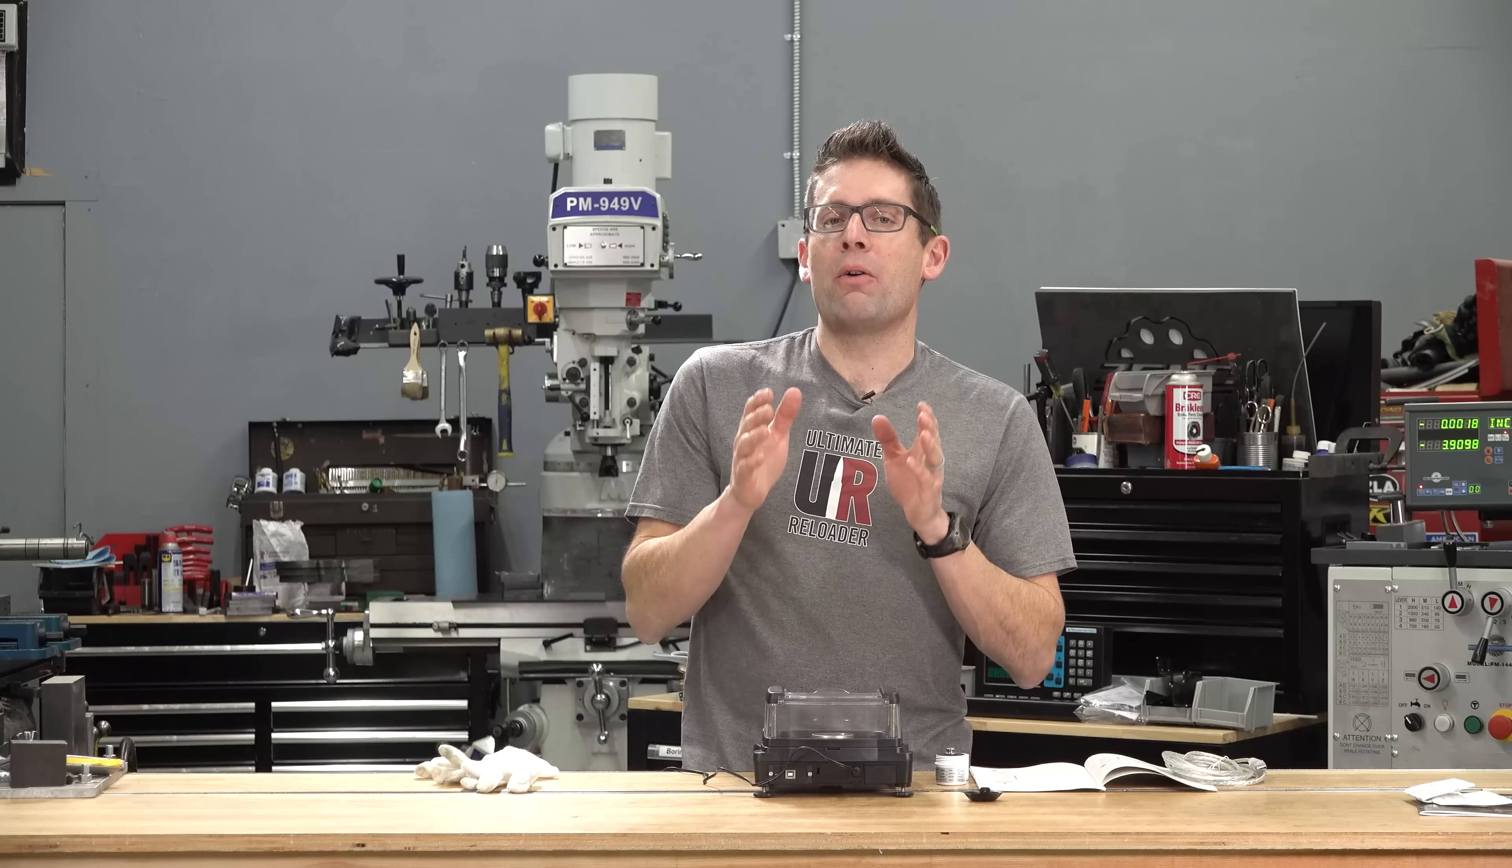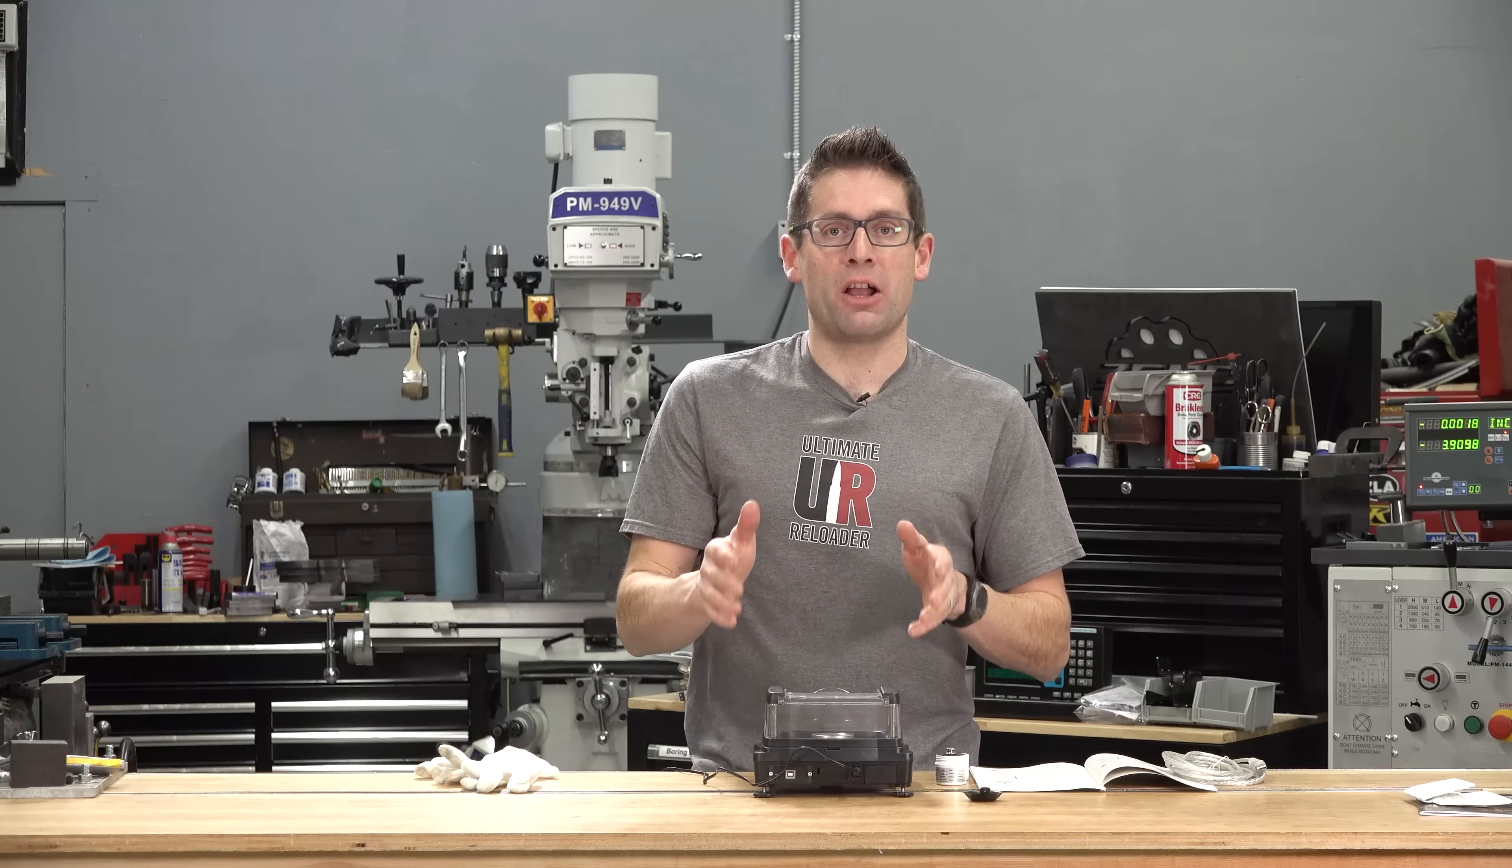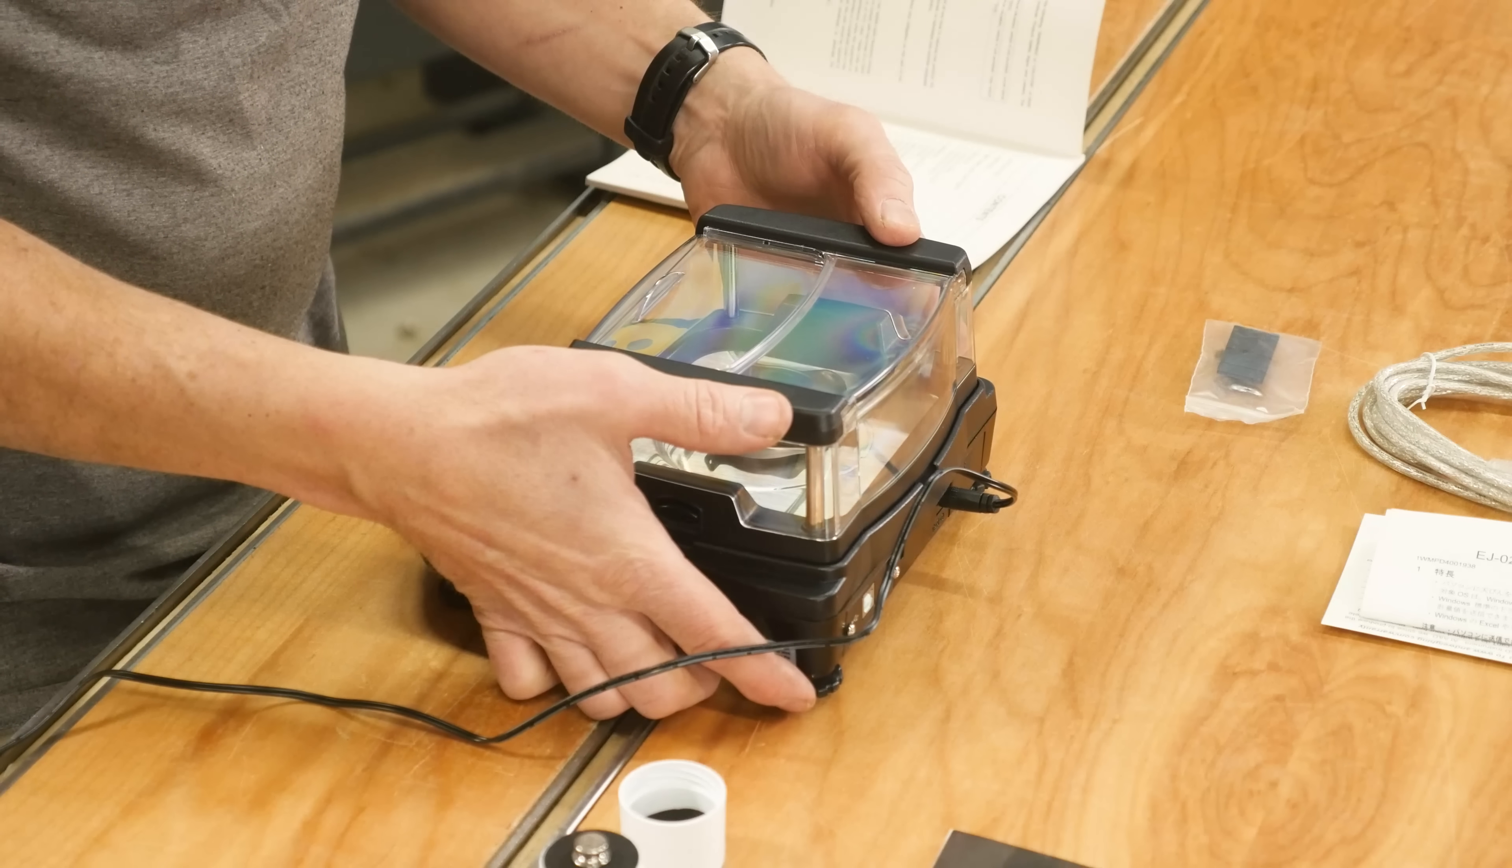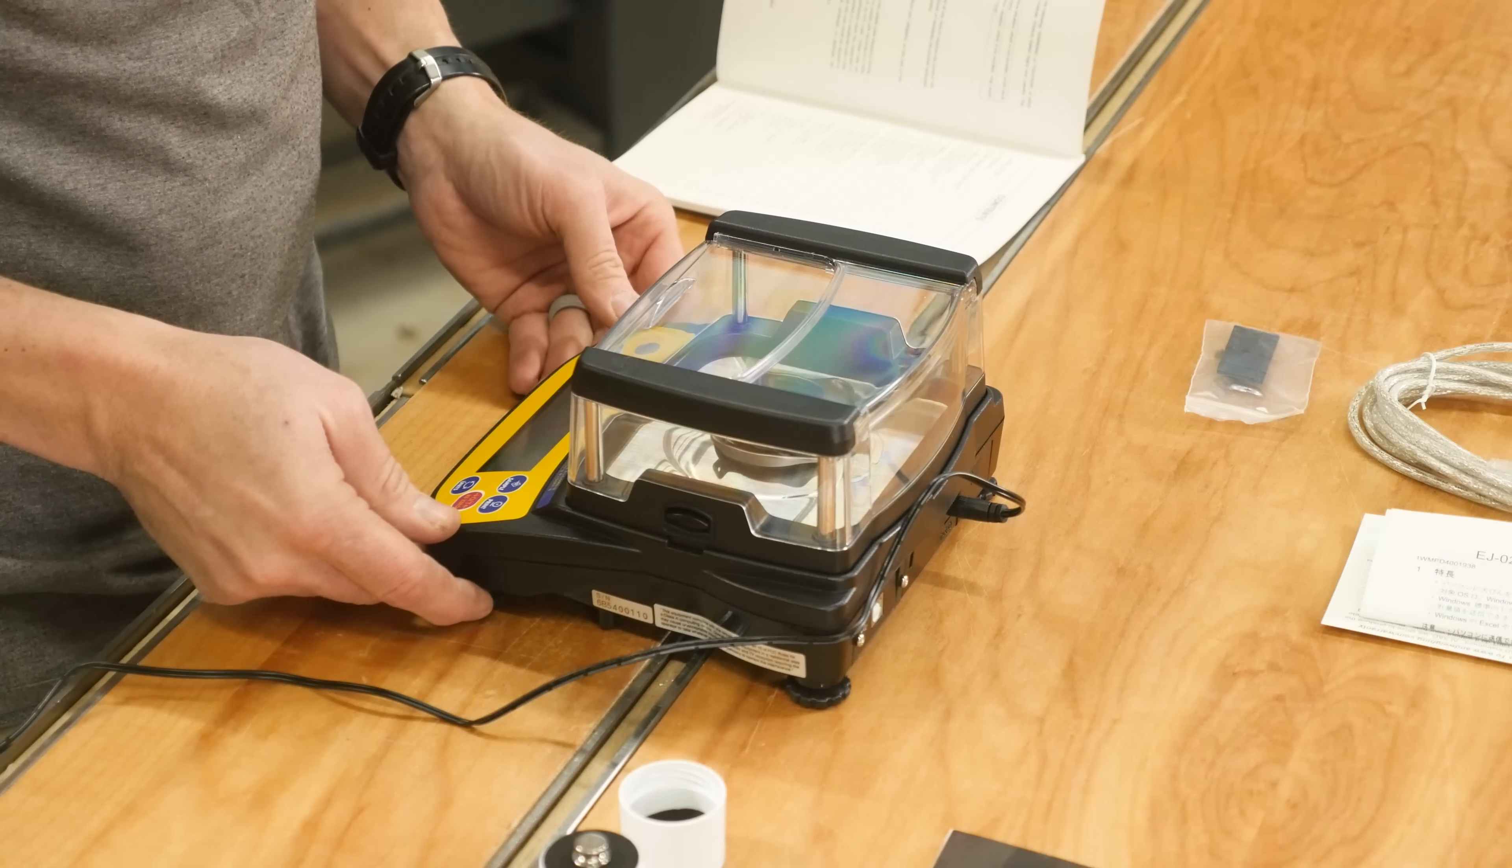I've had this scale powered up for well over an hour now, and that means I'm extra sure that this scale is up to temperature. It's running at steady state, and I should be good to go to calibrate now. One additional note, after the initial setup steps that I walked you through, I also adjusted all four feet. They're independently adjustable, and that allows you to use the integral bubble level to get the scale perfectly level.